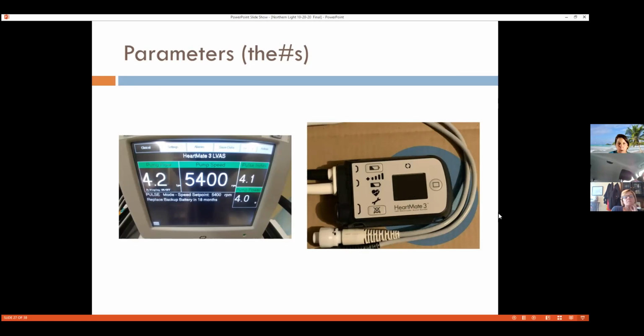One of them is called the flow, and I think of that as cardiac output. It's actually a calculated number on the pump. One is the pump speed. It's a fixed speed; that's how fast the pump is running. It's not going to vary. It's always trying to stay right around what it's set at. The pulse index is a number which is sort of additive information, which can tell us something about the patient's volume status and also their contractility. And the power, we want that number to stay very stable. If we see that power start to trend up, that could indicate a clot on the pump. So that in a nutshell is what we call the VAD parameters.